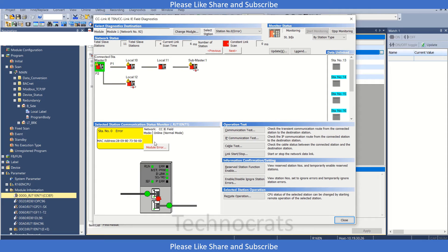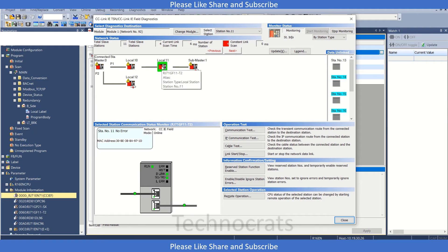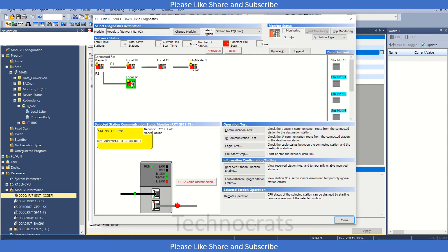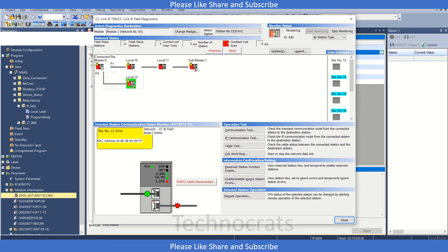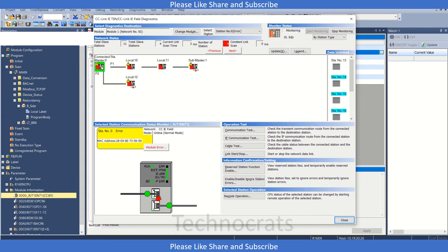In the network, local station number 10, both cables are connected. In 11 also cables are connected. In the submaster, the first cable is not connected. And in the 12th module, the second cable is not connected. So that means my network is not healthy because my submaster 1 and my local station 12 are not connected.